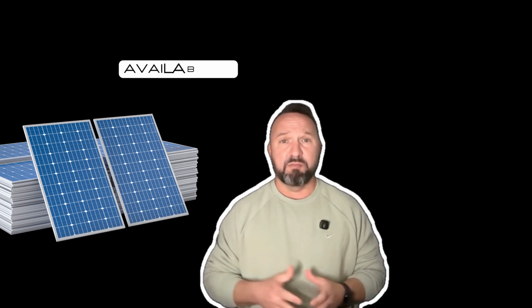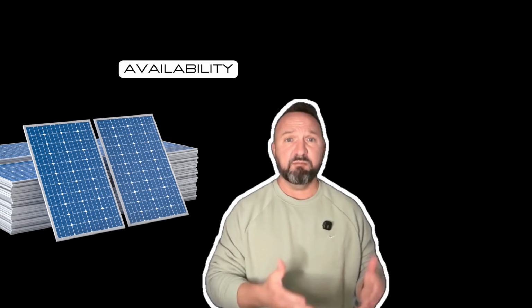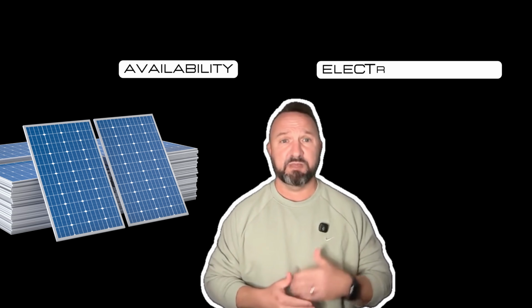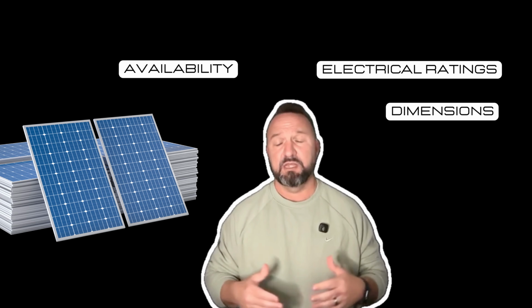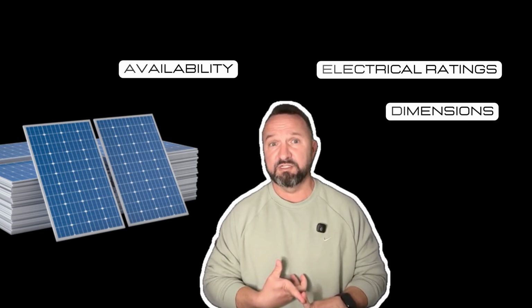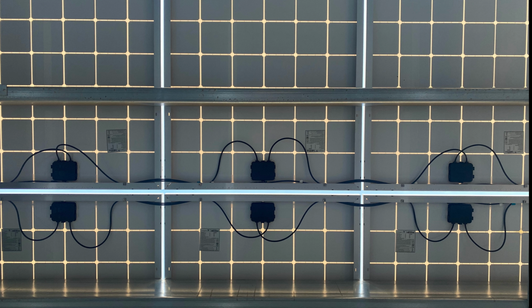So let's talk about why obsolescence matters based on each component. Well, solar modules degrade slowly over time, but the challenge is matching the replacements. So if a module fails 12 years after installation, the original model likely no longer exists. So replacement modules may have different voltage characteristics, power ratings, or even physical dimensions. And what this means is this affects the string voltage designs, maximum power point tracking for the inverters, and the mechanical mounting systems for these modules out in the field. Even a small electrical mismatch can reduce energy production across the full string.